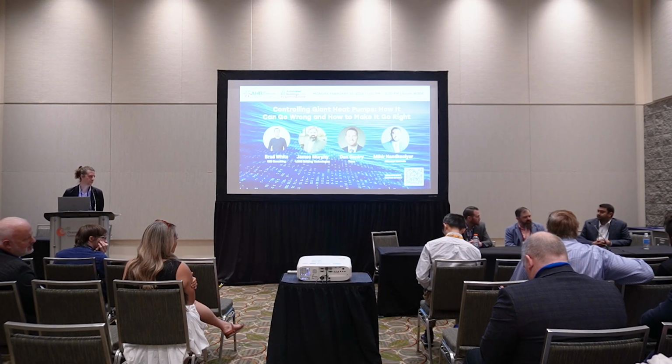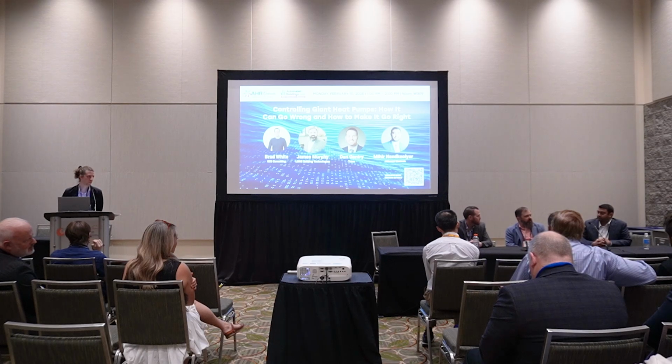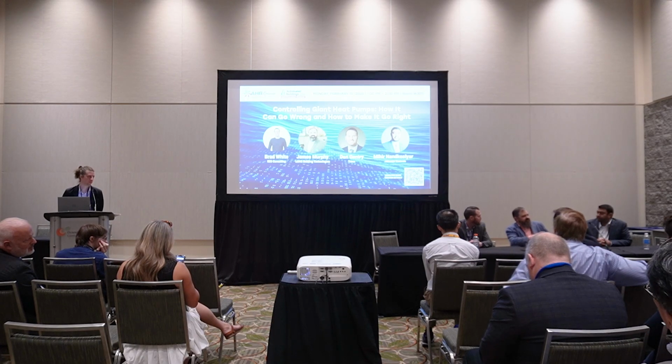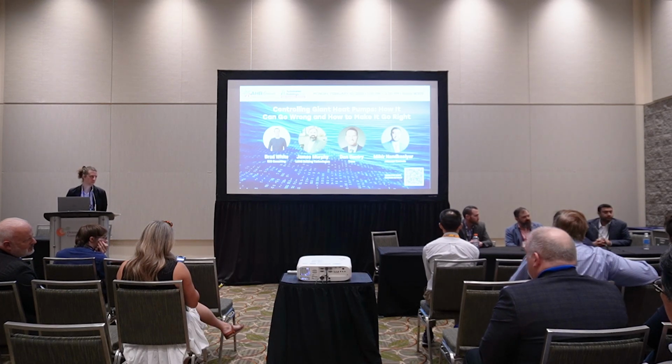The other thing I think is it really is product specific. If you're using a positive displacement compressor, you probably have a little bit more leeway. If you're using a dynamic displacement compressor, centrifugal or whatever, then there's some pressure you have to overcome. It's hard to do that. So all of those, you really have to worry about the compressor map and all that other stuff. So it really is product specific, but having a pony system, like a small one, or volume, or letting your temperatures kind of vary based off of the load, all of those are different strategies that will work.